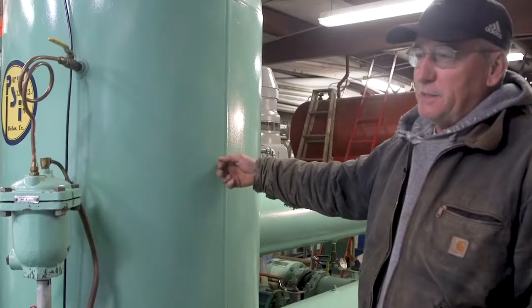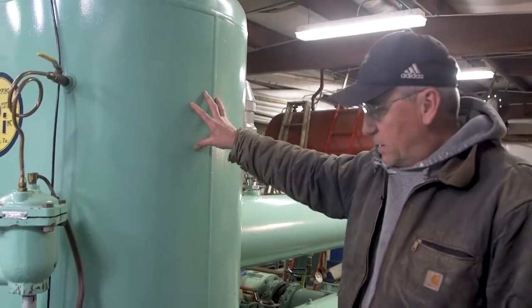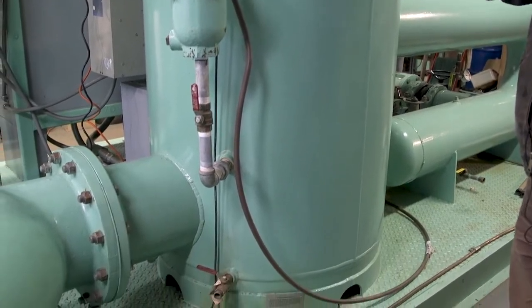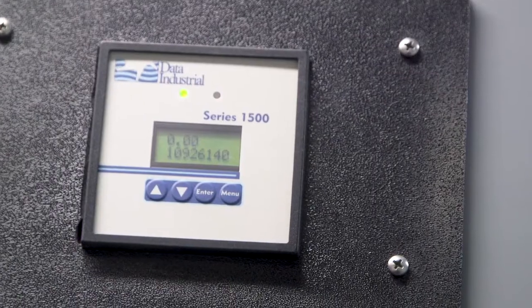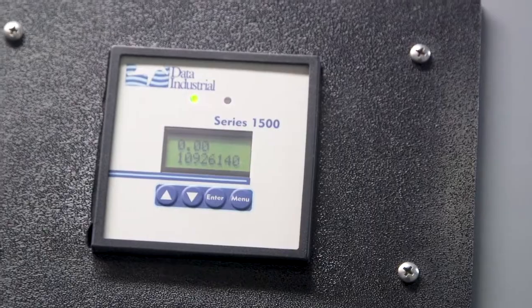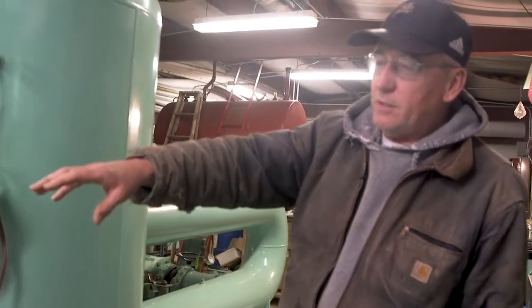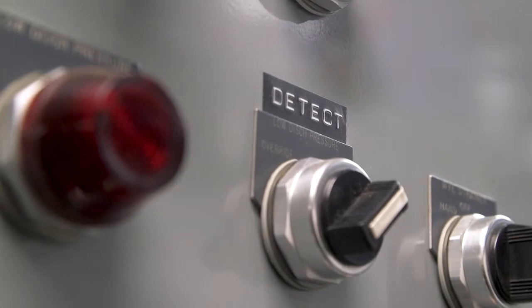These fixed speed systems are kind of unique. They have a big bladder, a big pneumatic tank that's half water, half air, and that's where the whole thing starts. And then it goes through a Y strainer, goes through the metering elements of the Cla-Val valves, and overnight that'll determine the up and down pressure of the whole system on demand.